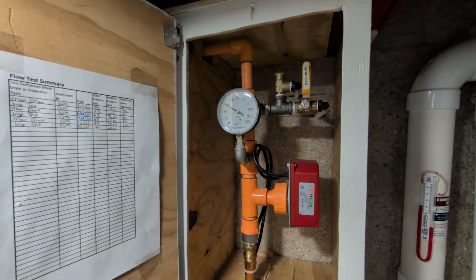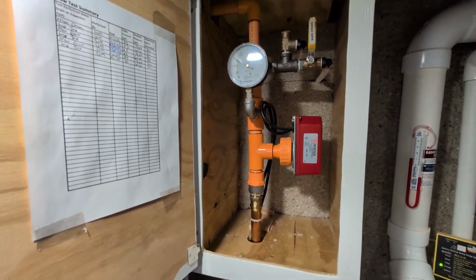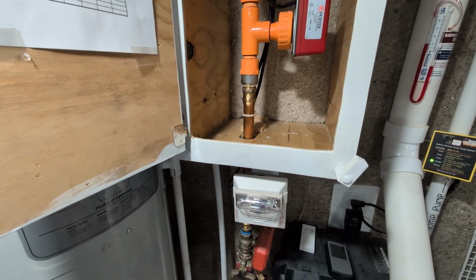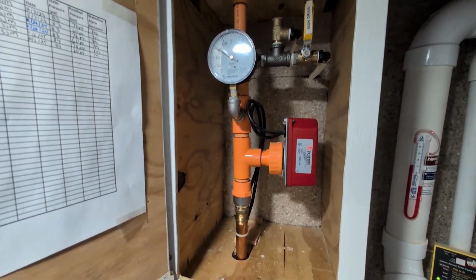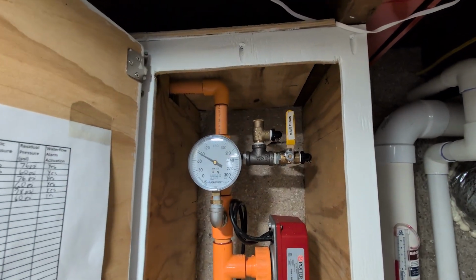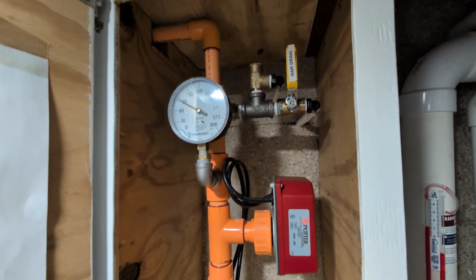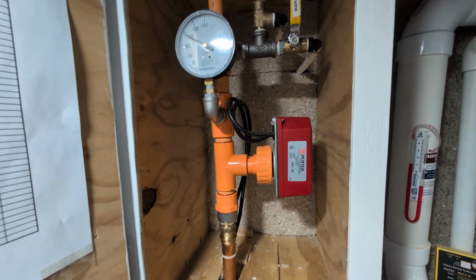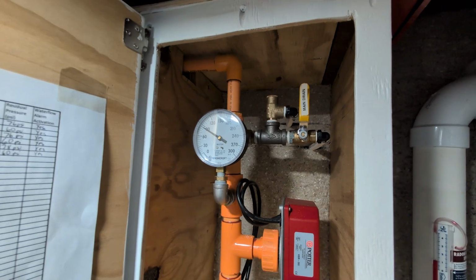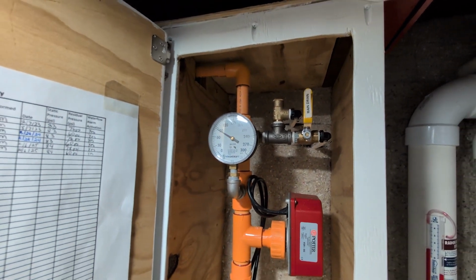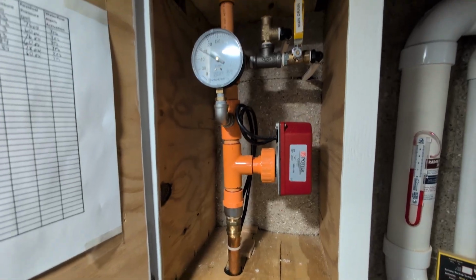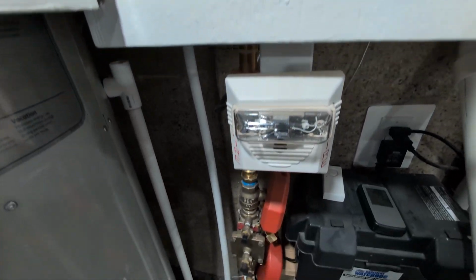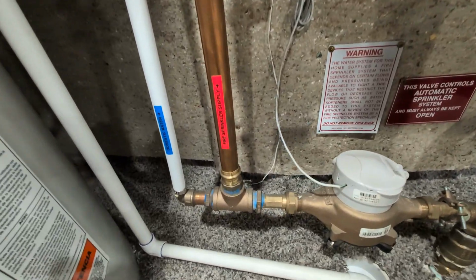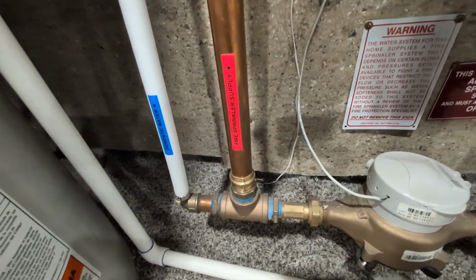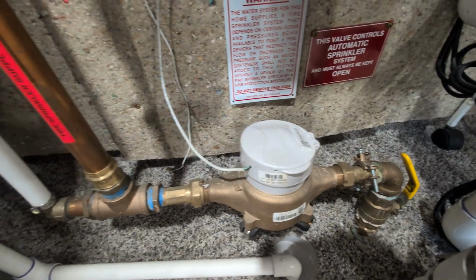Now, the first question that I get often is, what are some of the allowable water supplies for these types of systems? And there's a couple different options. So NFPA 13D allows you to do a multi-purpose type system, which means you actually use the same piping for your domestic water in your entire building, and that's also supplying water to the sprinklers. Or you can use your domestic water supply like this and have a separate one, so we've got domestic coming out on the left and our fire sprinkler system on the right. You can use that combined. You can use your domestic water supply.